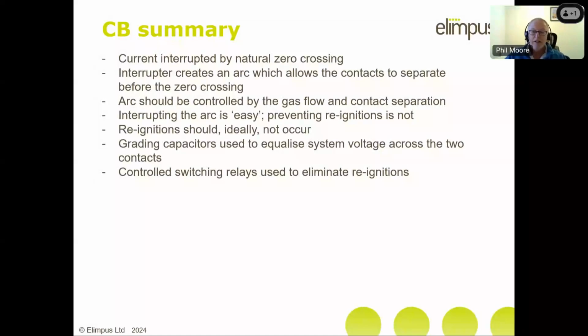Reignitions ideally should not occur. They are a problem in circuit breakers, especially in shunt reactors. We use grading capacitors because they equalise the system voltage across the two contacts when the arc's gone out. And finally, control switching relays are more or less universally used now. I don't think if you were putting in a transmission voltage shunt reactor today, you would use a breaker without a control switching relay. They're almost synonymous with good practice.